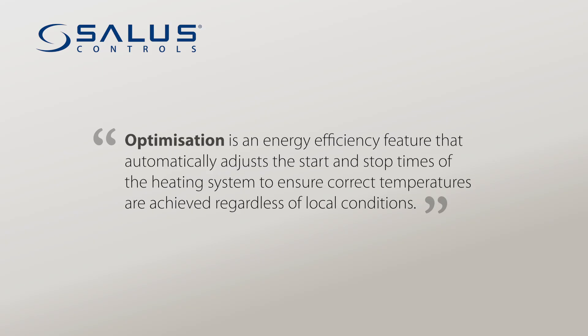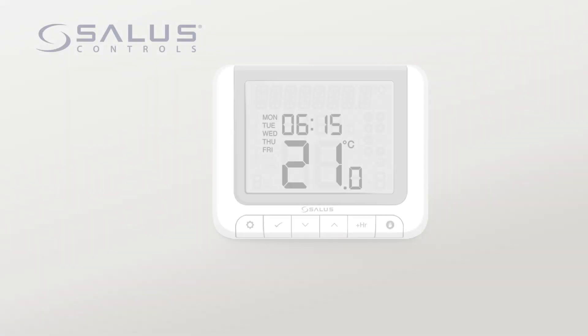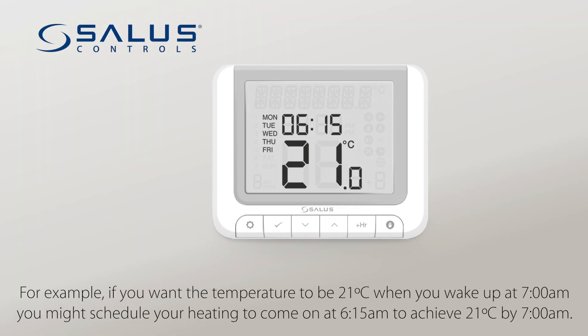Optimization is an energy efficiency feature that automatically adjusts the start and stop times of the heating system to ensure correct temperatures are achieved regardless of local conditions. For example, if you want the temperature to be 21 degrees Celsius when you wake up at 7 a.m., you might schedule your heating to come on at 6:15 a.m. to achieve 21 degrees Celsius by 7 a.m.